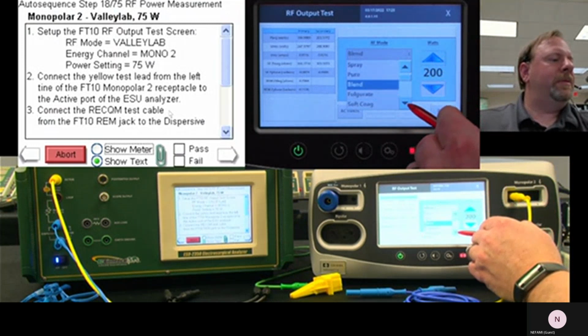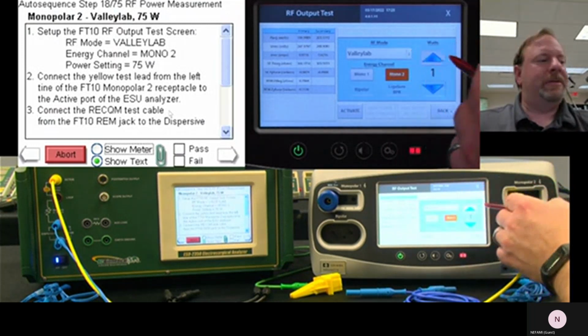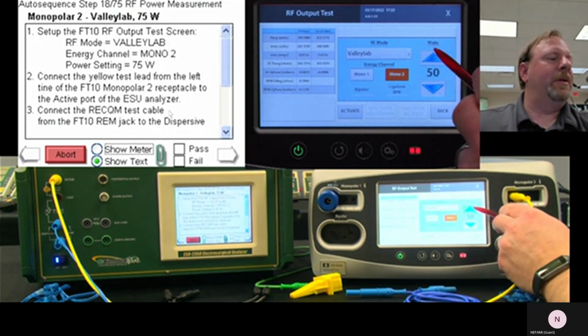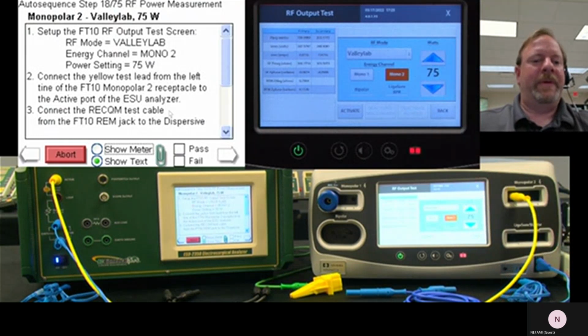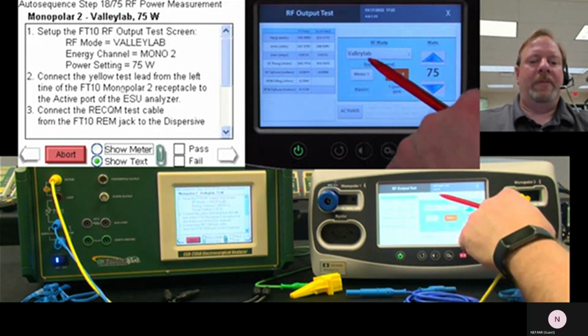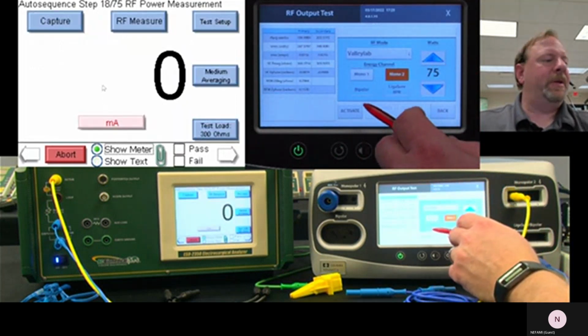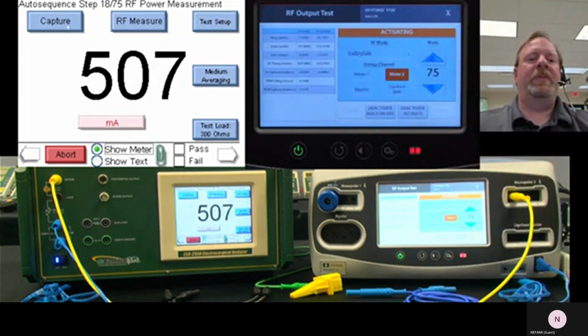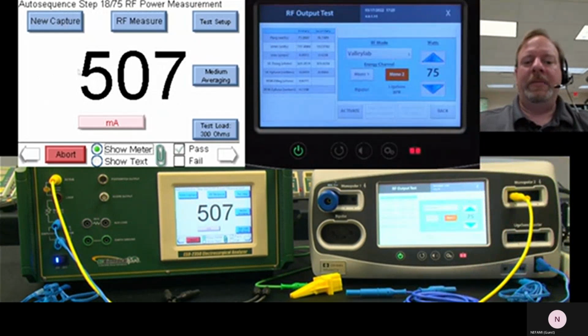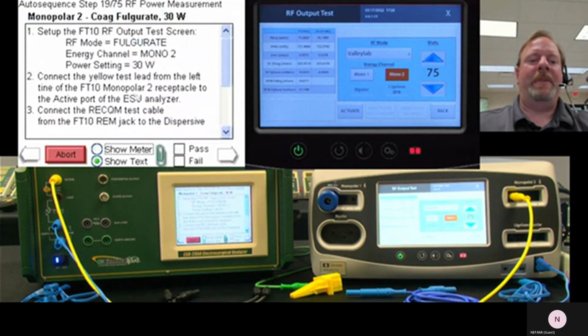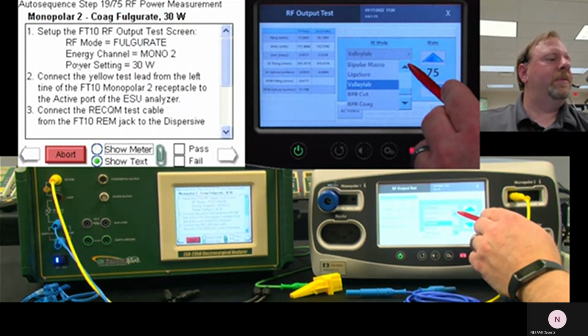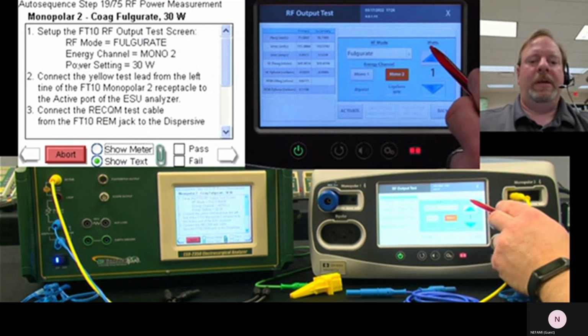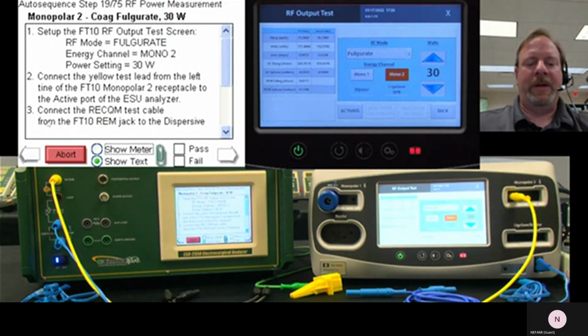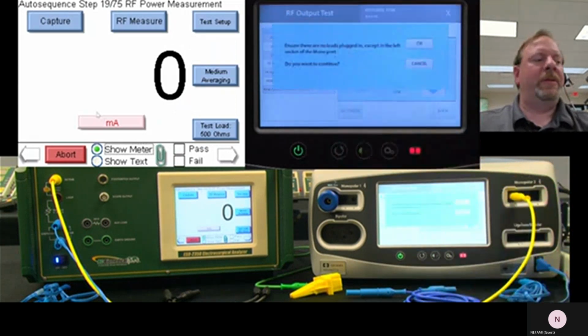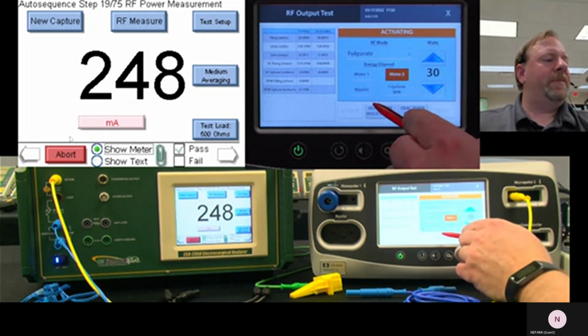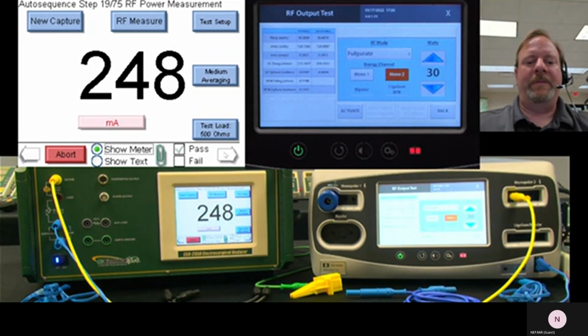So now we go to Valley Lab mode. Now these aren't alphabetical, so sometimes you have to hunt for which output you're looking for. But in this case, we found it fairly easily, 75 watts. Again, we're still monopolar 2, so we're good to go with our connections. Show meter, activate, confirm you want to activate. I really do. I did push that button. Okay, we got a measurement. We move on. Fulgurate now, and 30 watts. So different power levels, different waveforms, same connection, so I don't have to move anything. Do a capture, deactivate. So this time we're at 500 ohms.